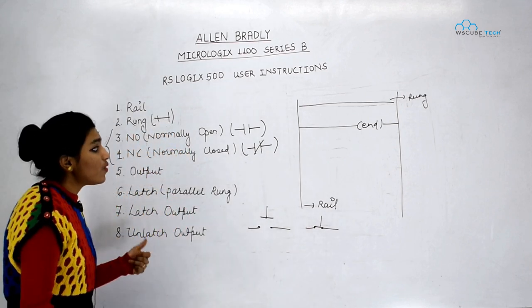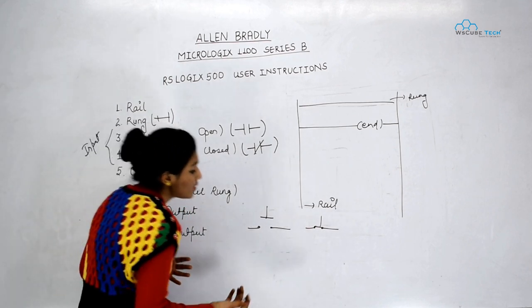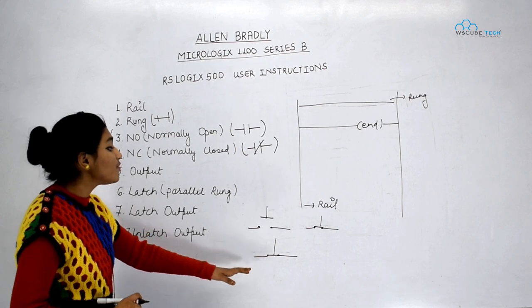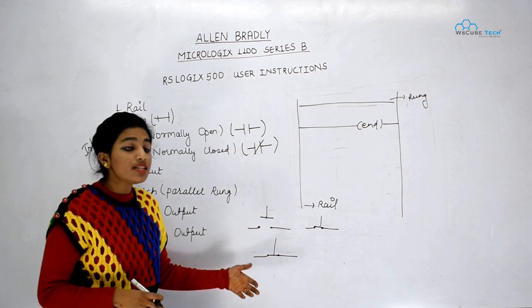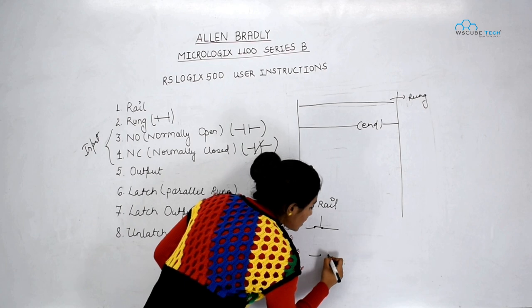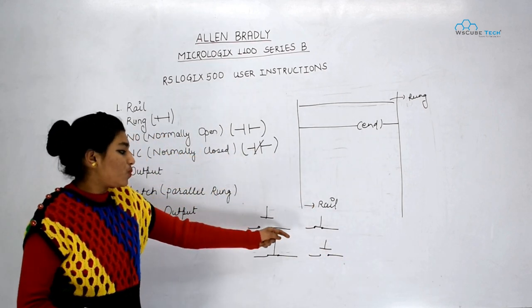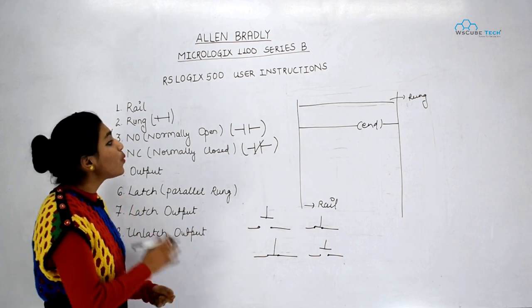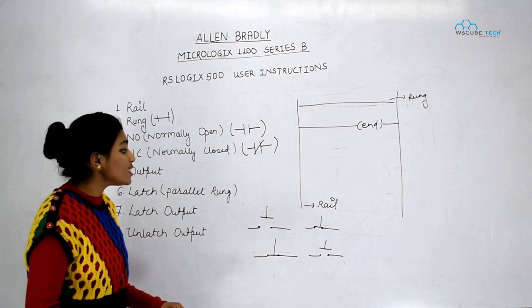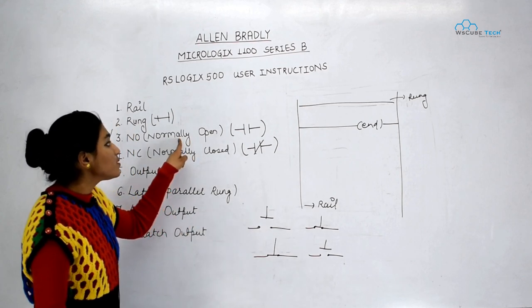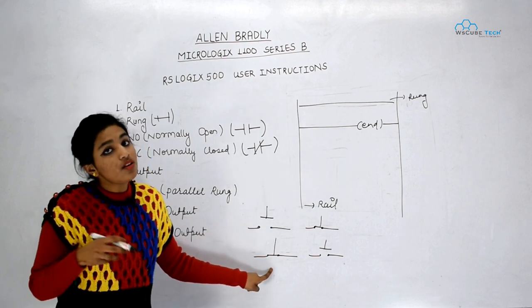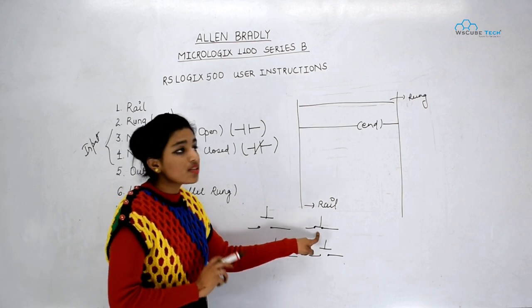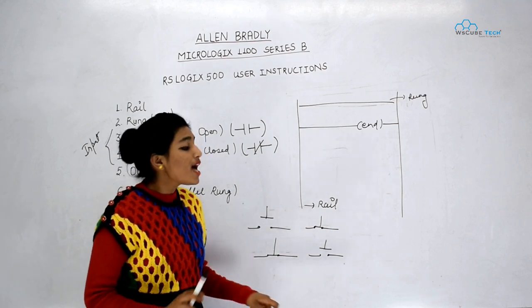Now let's come to NC — Normally Closed. In the released condition, the structure of NC is such that signal is still flowing. When I press it, it is just opposite to NO. Comparing NO and NC, both are opposite to each other: when the push button is released, from NO signal was not flowing but in NC signal was flowing. When pressed, in NO signal flows but in NC the circuit breaks and signal will not flow.